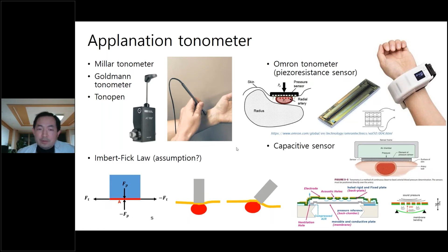So to overcome the size and the difficulty in use, for example, the Millar tonometer always requires a perpendicular, very appropriately applied position over the radial artery, and if the applanator is not in a perpendicular position, then the measured pressure is not the real artery pressure. Also, if the Omron tonometer is not appropriately applied in a perpendicular manner, it will make a similar result with a similar error as the Millar tonometer.